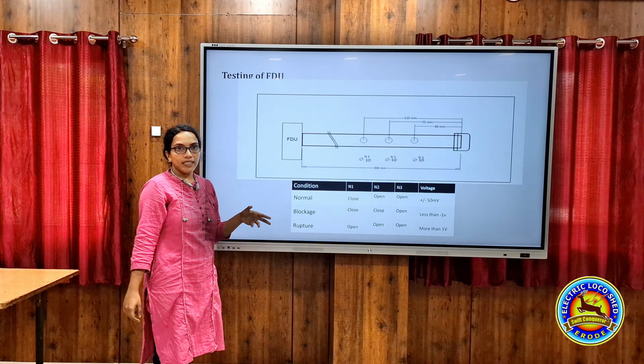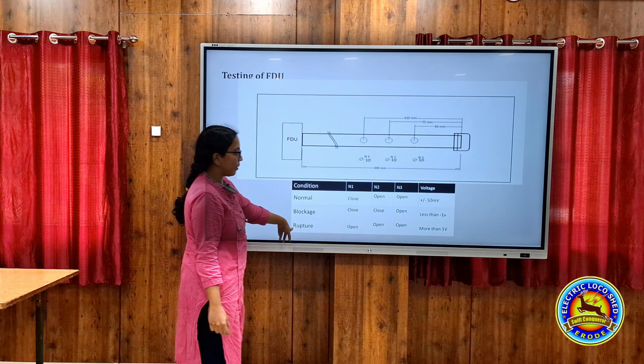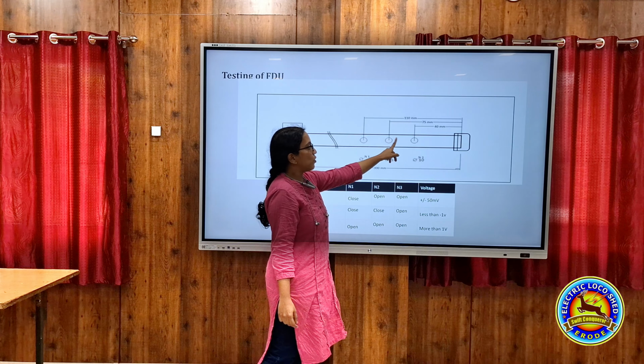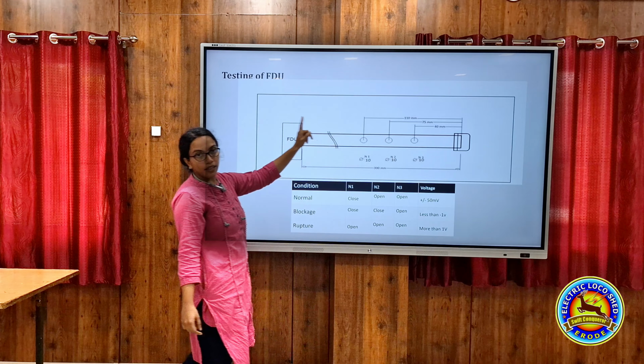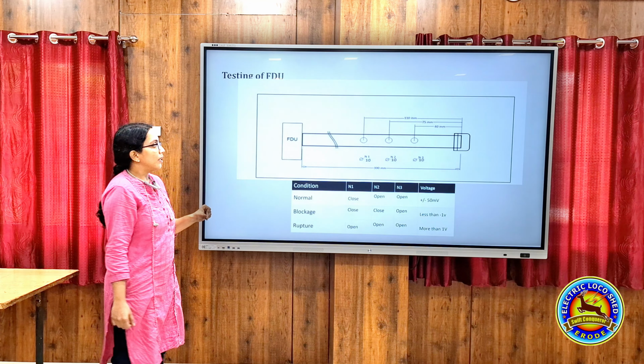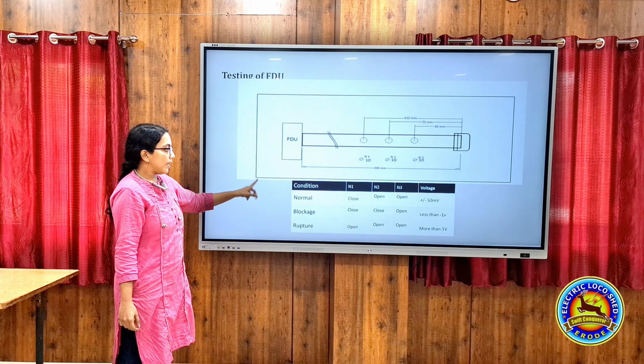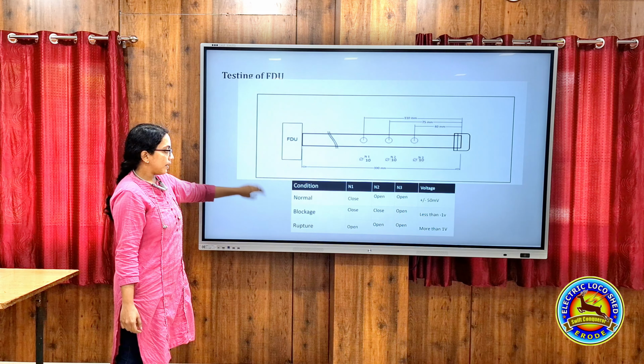The voltage should be less than minus 1 volt. And for rupture, all the three holes will be opened. The voltage should be greater than 1 volt. In these conditions, it would show the malfunction of FDU. These two conditions. This is the FDU test bed. This is the 24 volt power supply. This is the pipe we connect, and this is our FDU.